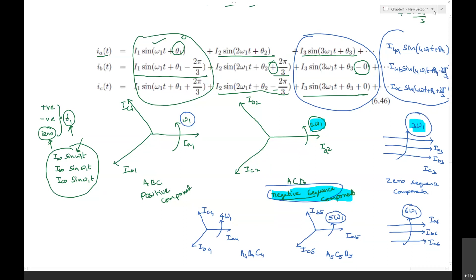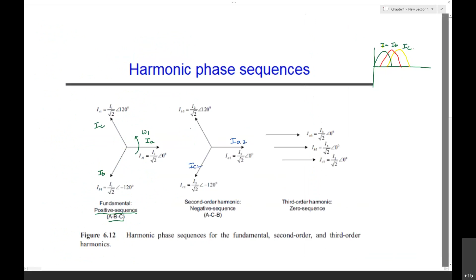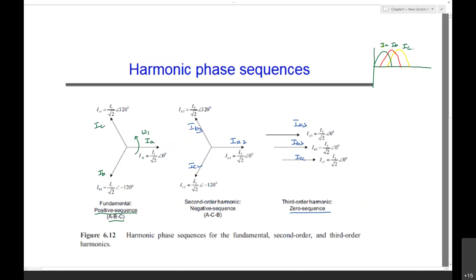Okay. These are the second harmonic, which I was just mentioning, IA2, IC2, and IB2. This is about IA3, IB3, and IC3. The third harmonic represents the zero sequence. Here is a tabular column. The harmonic order of 1 represents the positive sequence. The second harmonic order represents a negative sequence. The third harmonic represents the zero sequence. The fourth harmonic is positive sequence, the fifth harmonic is negative, and then the sixth harmonic is zero sequence.